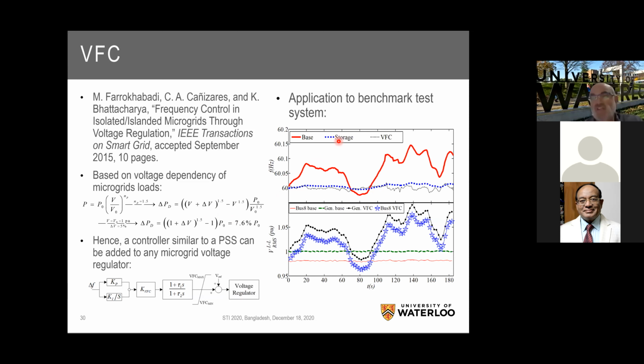When you introduce this type of control, you basically behave almost like an energy storage. The dotted line is the energy storage, and the blue or black line is what you accomplish with this type of control, which has its limitations depending on the limits of the system. Basically, you are effectively using the load as a dispatchable load without affecting the load itself, which is very important. The load isn't involved in deciding to participate; you just regulate the voltage, and indirectly you change the power.